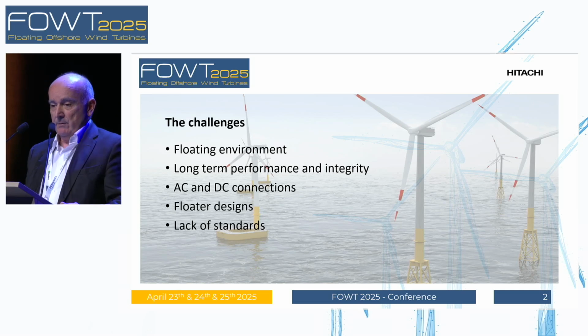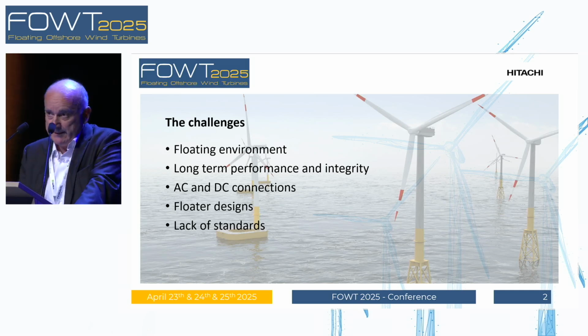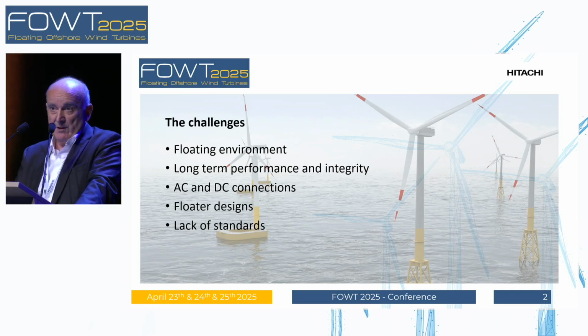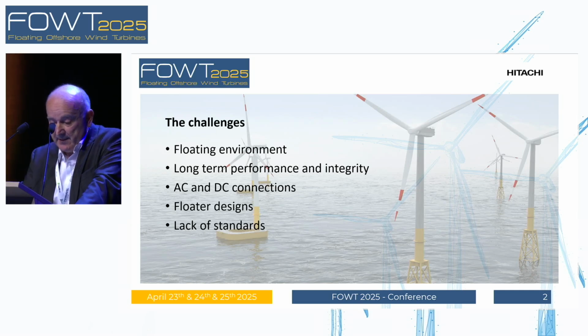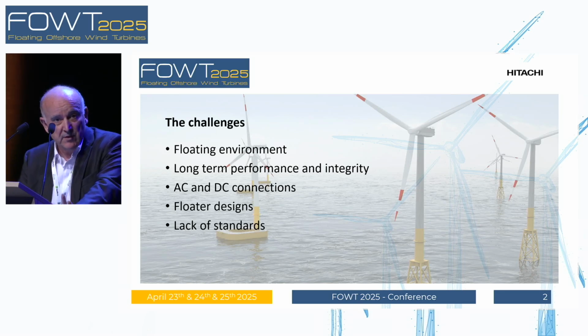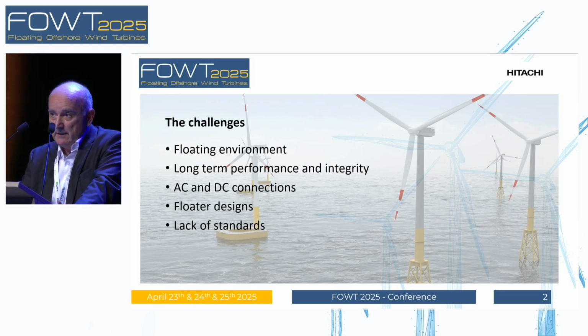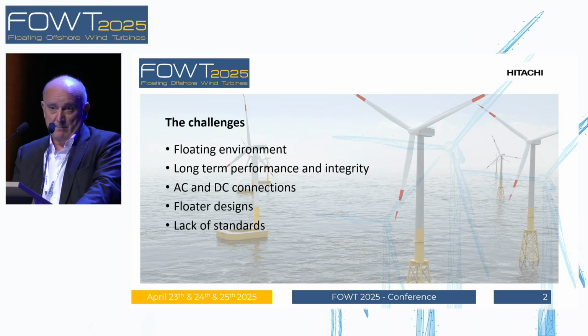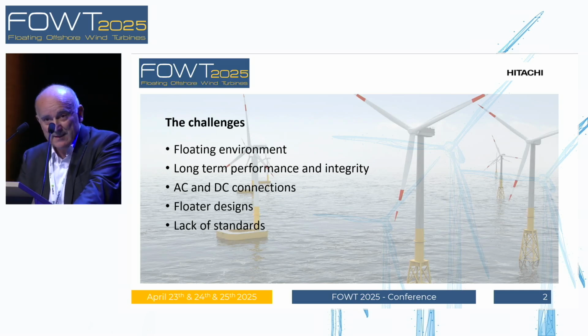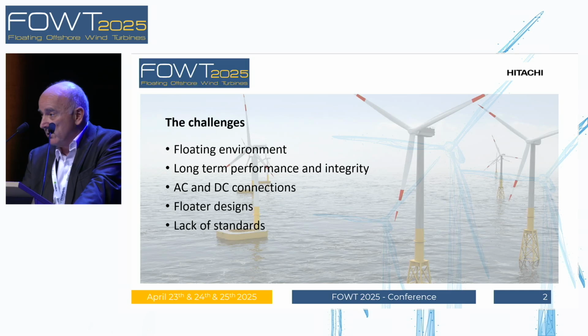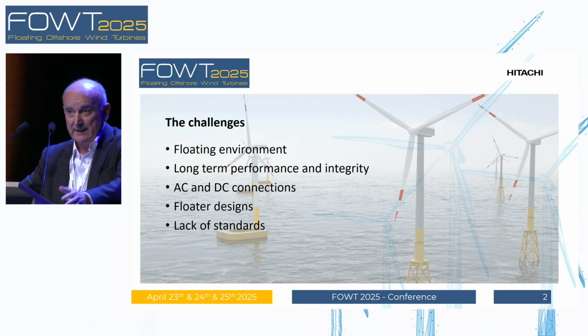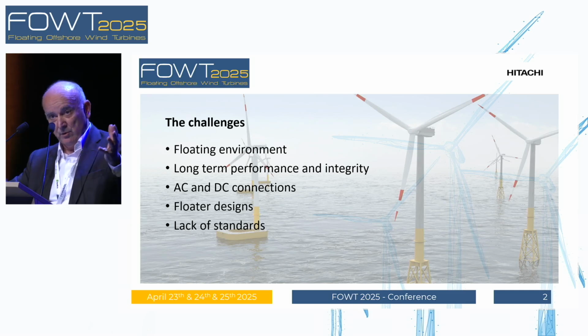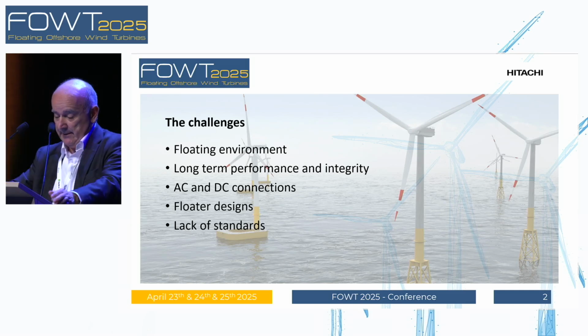The last point I will mention is standards, which was also referred to by Anna. We don't have standards for high voltage equipment in this environment, and this is critical. We know by experience that if you start designing, constructing, and commissioning without a standard, it's a very good recipe for big challenges. We had our part of it when we built our first HVDC converter station for Germany, where we faced many challenges during execution, and I would say 90% of them were related to the fact that we didn't have a standard that could align the OEM, the yard, and the investor.